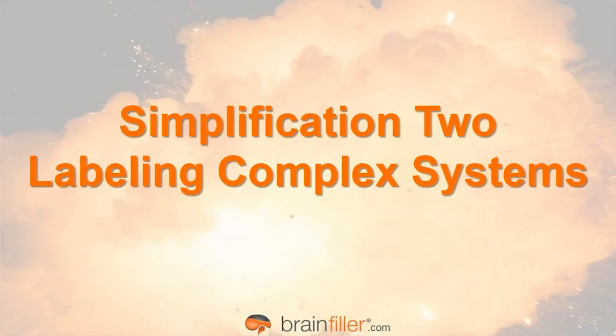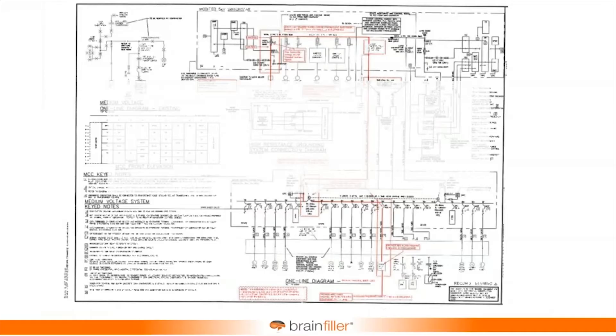Another labeling strategy — and this is actually brand new for the 2018 edition of NFPA 70E — is labeling complex systems. By complex systems, what I'm referring to is if you perform an arc flash study, use the software and perform calculations, you look at a more complex single line drawing.